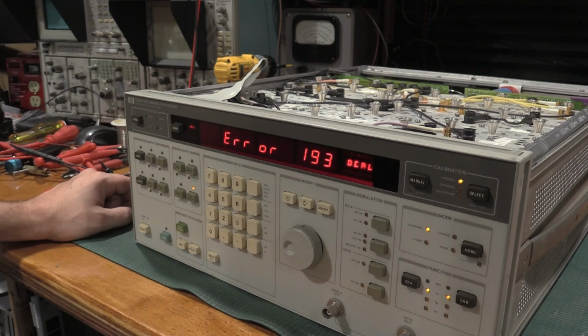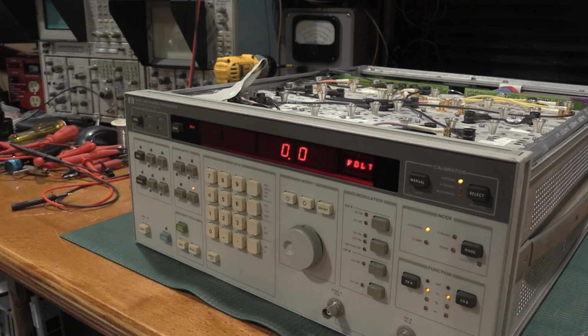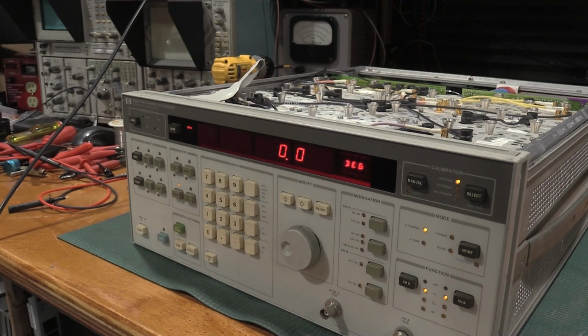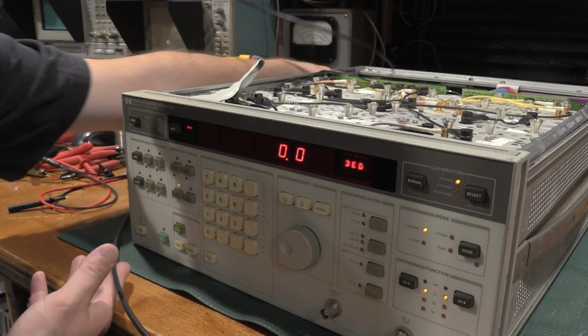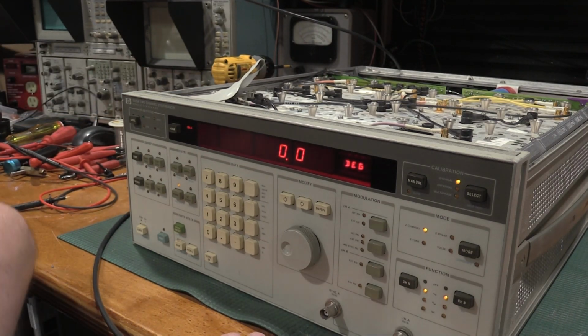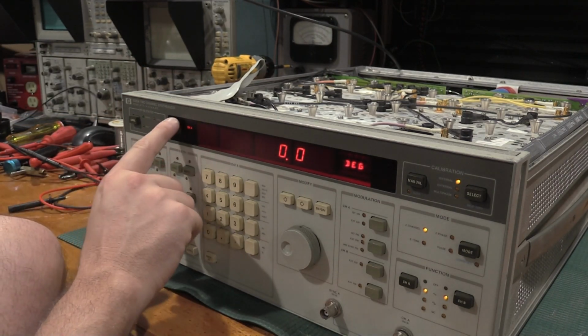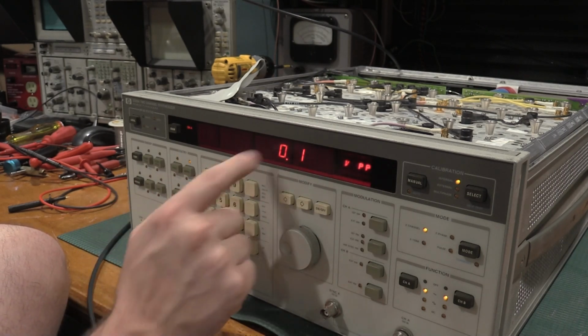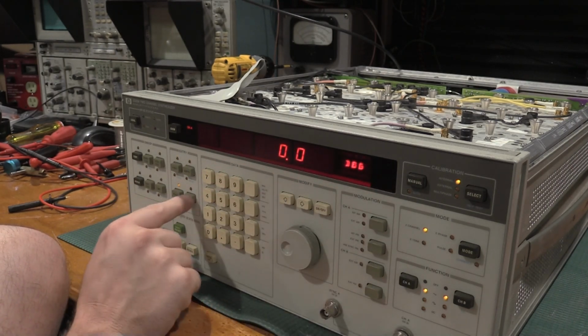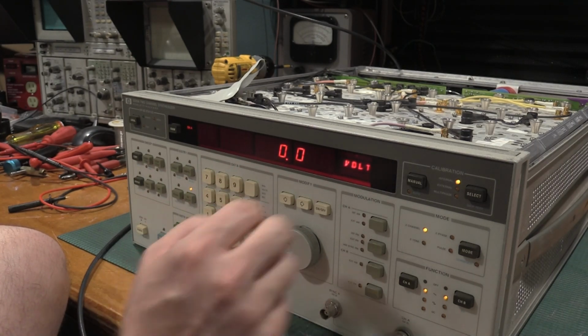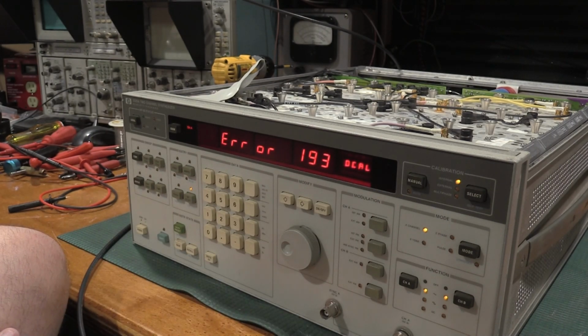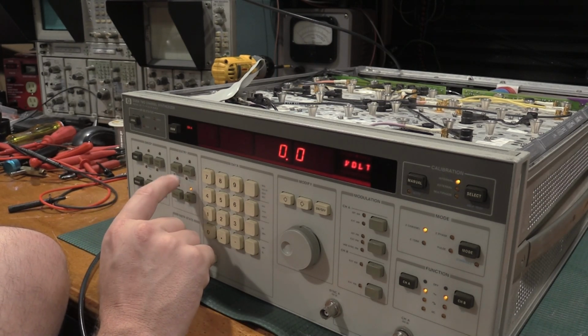Except now it's not happy at all, and it was before. So what's it actually doing? After playing around with some settings and running the self-cal a bunch of times, just trying to figure out where the problem is, messing around with some parameters because it doesn't really tell us much - on channel A we have 1 kilohertz, amplitude of 0.1 volts peak to peak, no phase, no DC offset. We can calibrate it and we get an error, which we didn't the last time I calibrated it, so it's still drifting around a little bit.